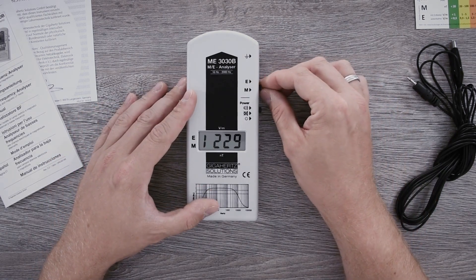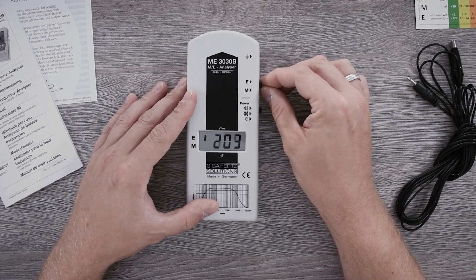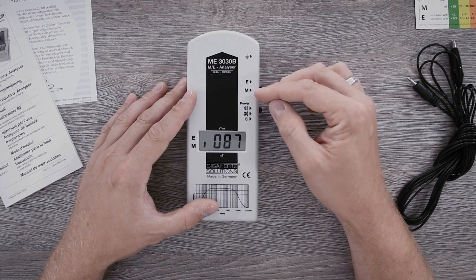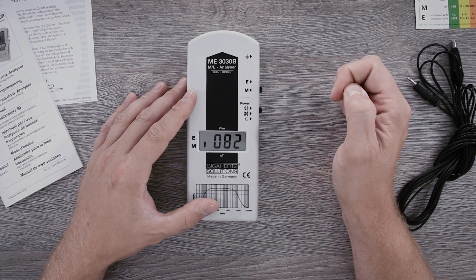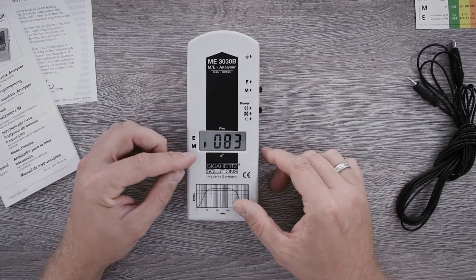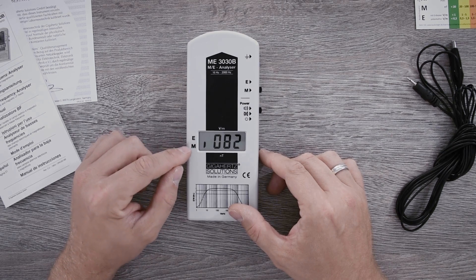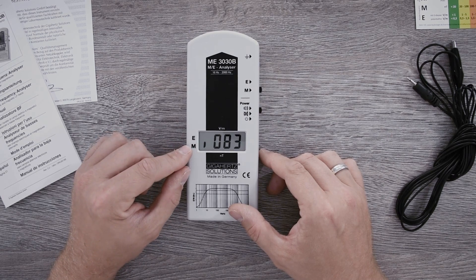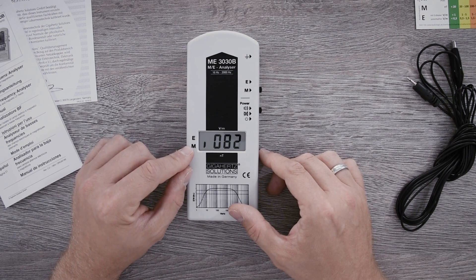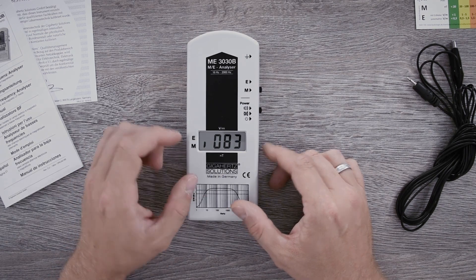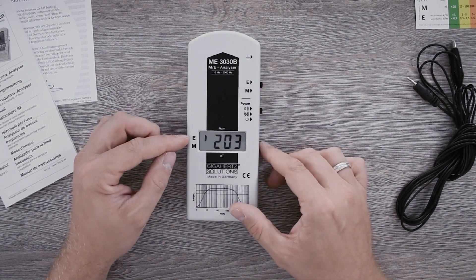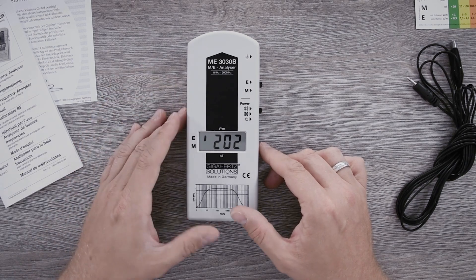Via the signal switch up here, you can now choose between E for electrical field and M for magnetic field. Depending on your choice, you can see this little line in the display symbolizing if the measurement is active in E or M as well. The magnetic field is measured in the unit nanotesla, and the electric field in the unit of volt per meter.